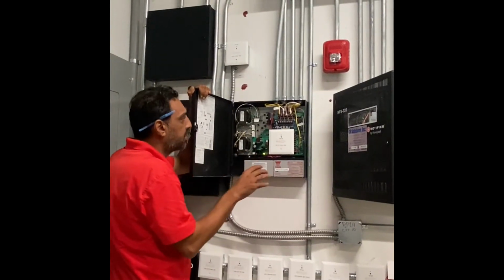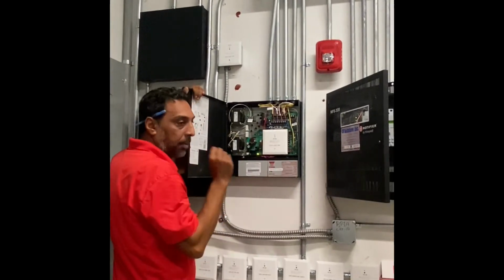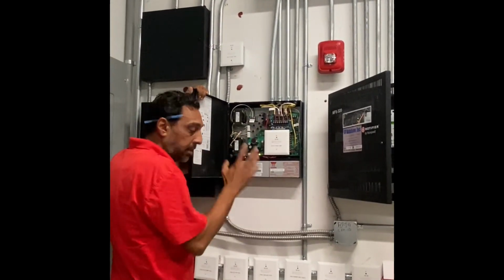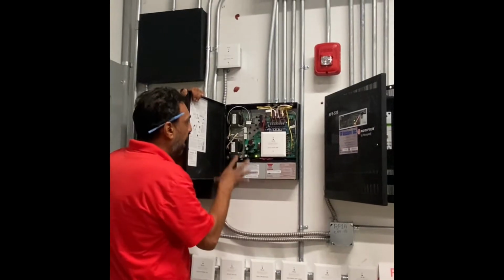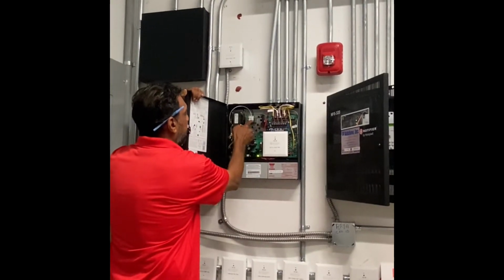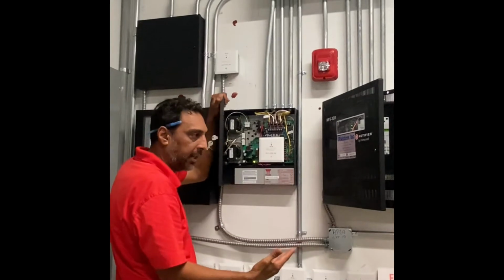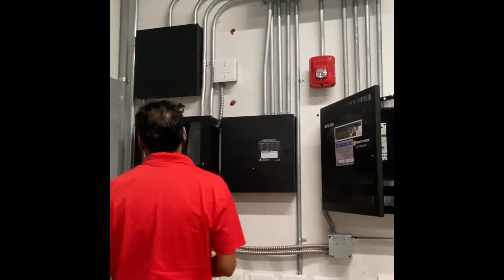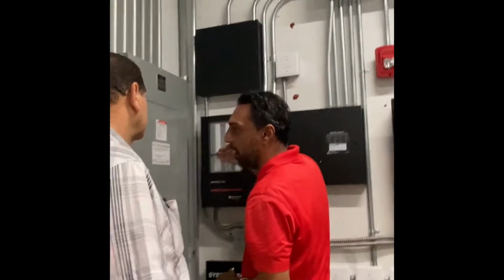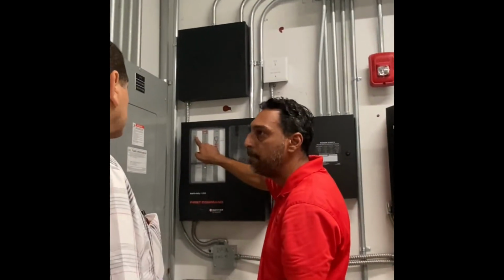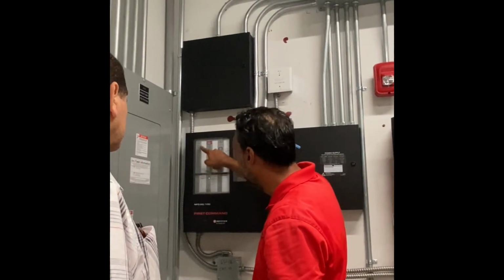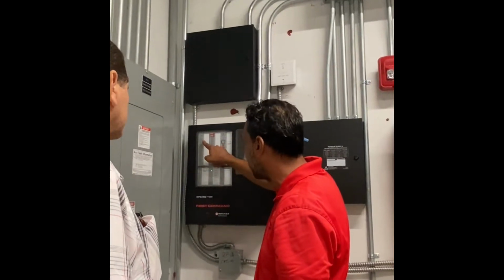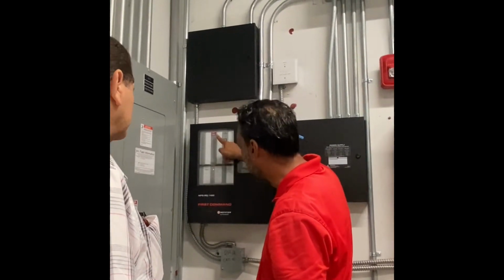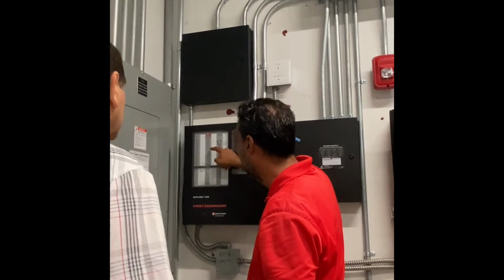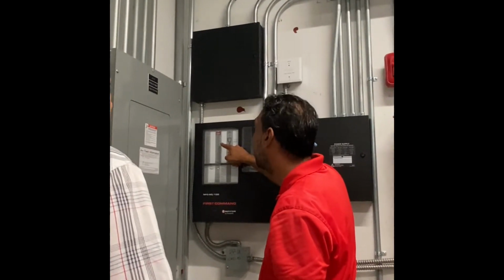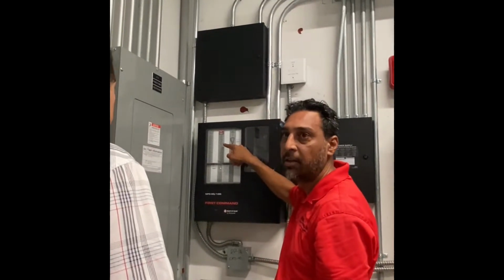If it blinks once, that means NAC 1 is in trouble. If it blinks twice, NAC 2, and so on, 3, 4. It'll blink how many times that device is in trouble, or what circuit is in trouble. On this, for the voice, it'll tell you your speaker circuit. That will go yellow, and 1 through whatever, that speaker circuit. So if there's a trouble on any of your speaker circuits, I think you have 12 or 13, maybe 16 on here. Something like 16 circuits on your speakers.